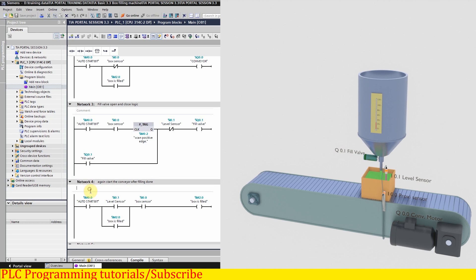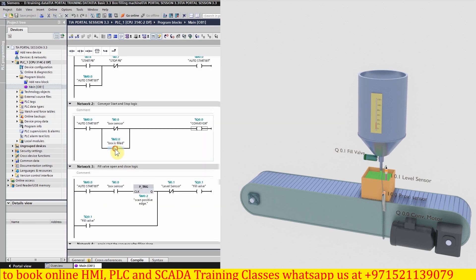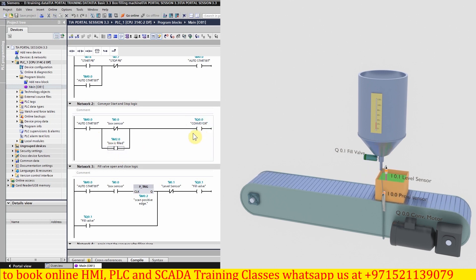In network number four we have the logic to start the conveyor after the box is filled. We have the auto start bit M 0.0, and once the level sensor turns on confirming the box is filled, it should turn on bit M 2.0 — box is filled. We insert its normally open contact in parallel to latch on bit M 2.0, and we insert this bit in parallel with the box sensor in network number two, so it will start the conveyor again to remove the filled box from the station.